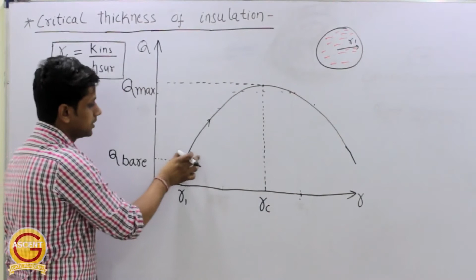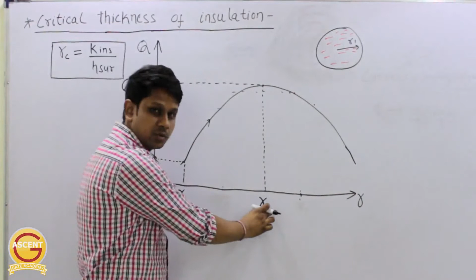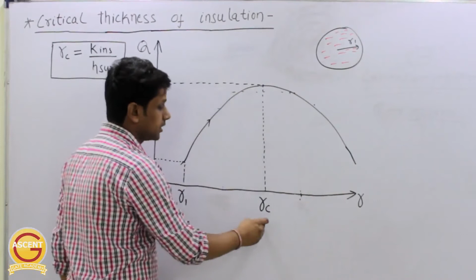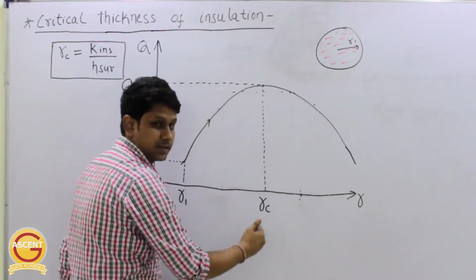So if this was the heat transfer without the insulation, the heat transfer is going to increase if we are using an insulation equal to or less than this critical radius of insulation. Fine. But our requirement is we want to reduce heat transfer in this case of pipes. So you can easily tell what should be the favorable radius of insulation. It must be greater than this critical radius of insulation, because in this region only, by increasing the radius, we can reduce the heat transfer, right? So this is the importance of this.